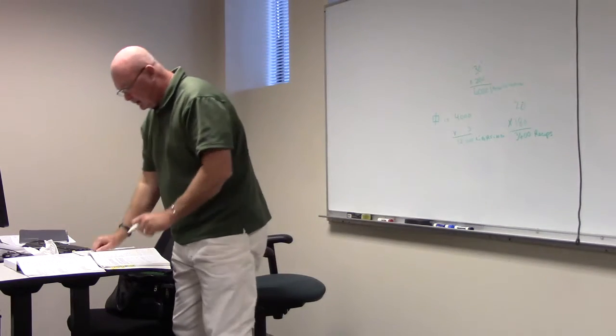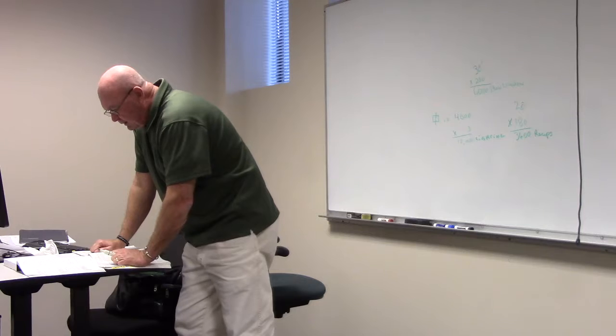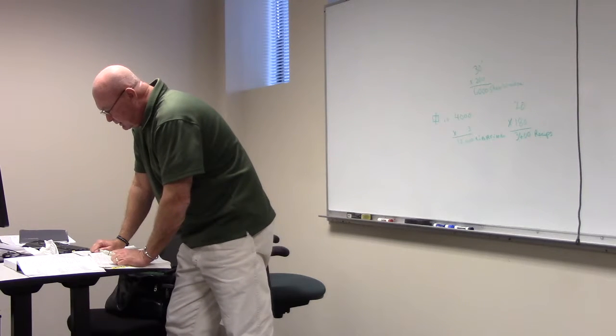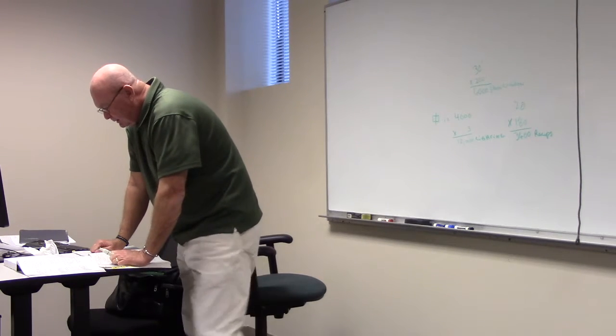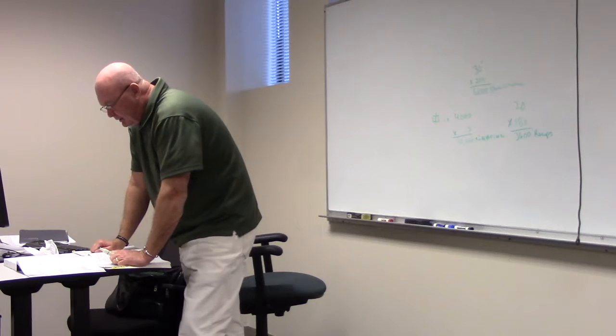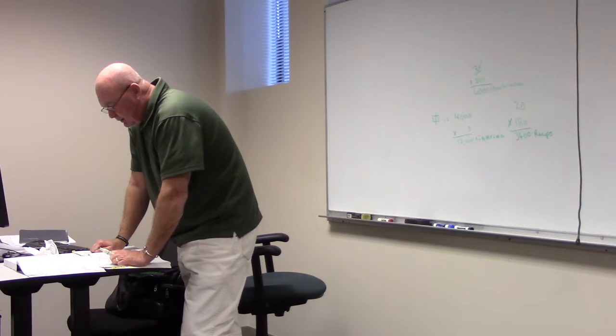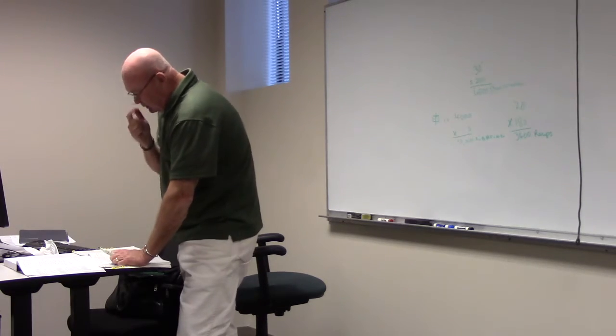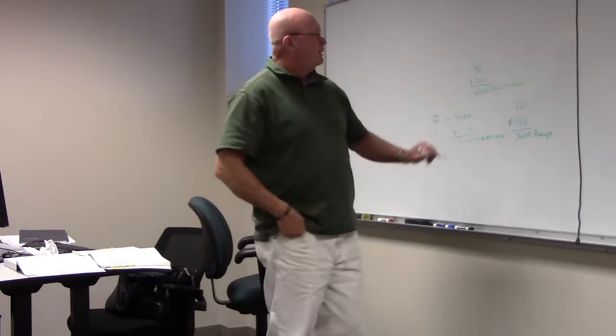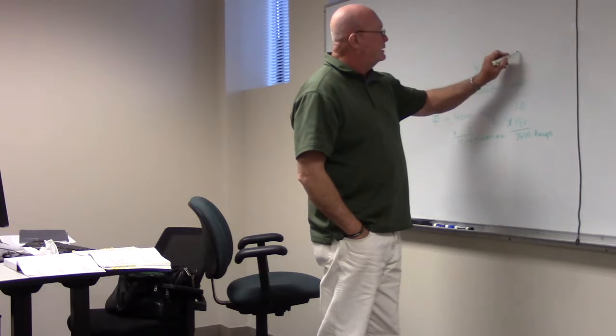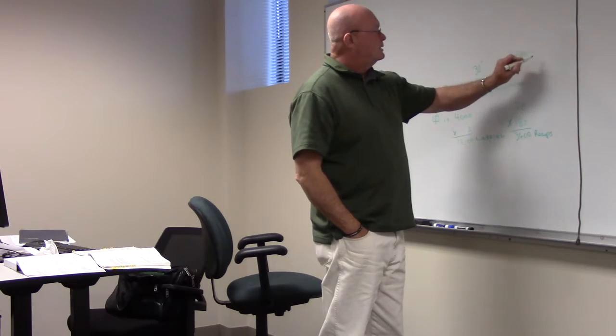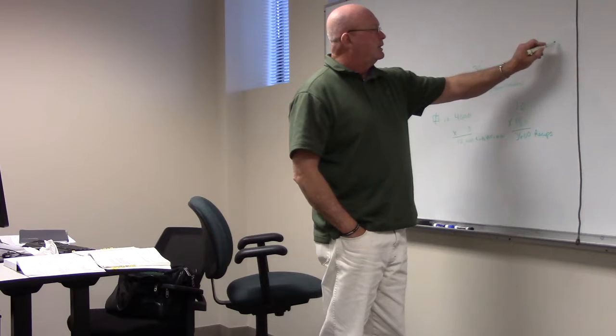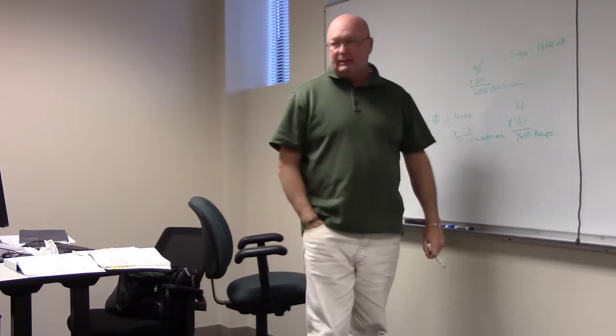Let's see what other kind of load we have. All right, sign. You see that there on the drawing? It says sign outlet. Look at step 5. It says allow 1,200 volt-amps outlet for sign or outline if the store is on the ground floor. If the actual load of the sign is not known, then we're going to use 1,200. We don't know the sign; it just says there's a sign outlet. So our sign, by the code, is 1,200 VA.